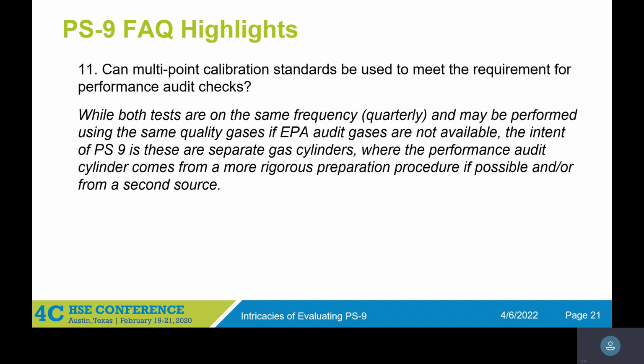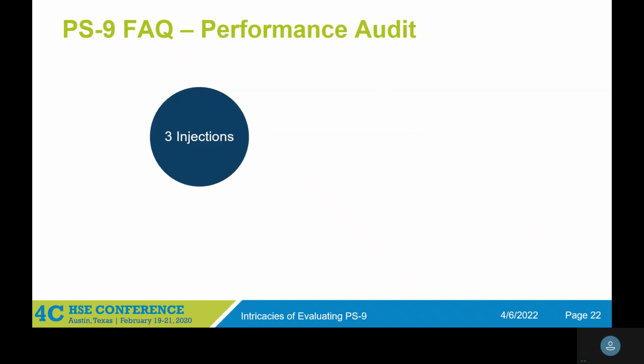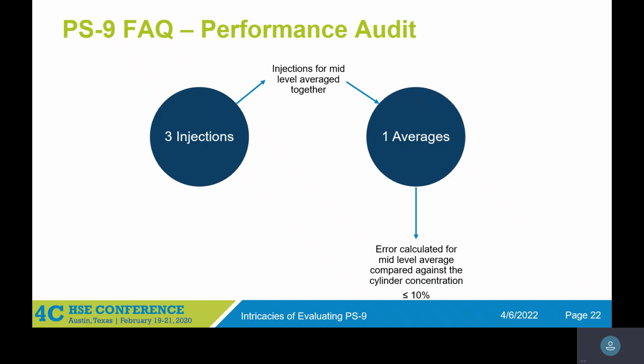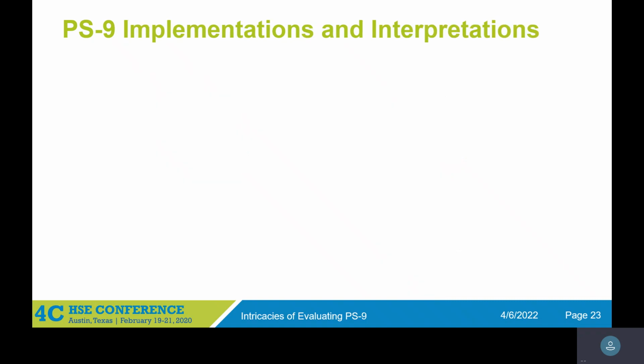And this last part, from a second source, seems to indicate that you might not want to use your triplicate PS9 test that you ran through the sample system also for your performance audit. With that performance audit, just specifying this out again: 3 injections averaged together into 1 average, and then that compared against the cylinder concentration to make sure it's within 10%.